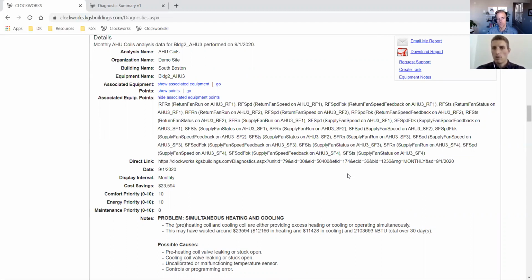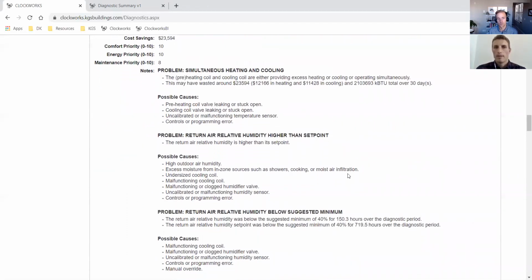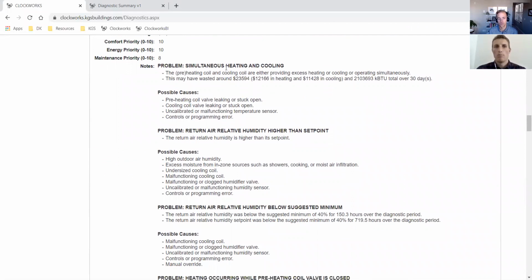Because we're doing this all holistically, we can generate these simple statements that tell you problems and possible causes. So my problem of simultaneous heating and cooling is where we're wasting a lot of money—in the last month, we've wasted $20,000 on this one issue. The possible cause we list first here is that you have a leaking preheating coil valve.